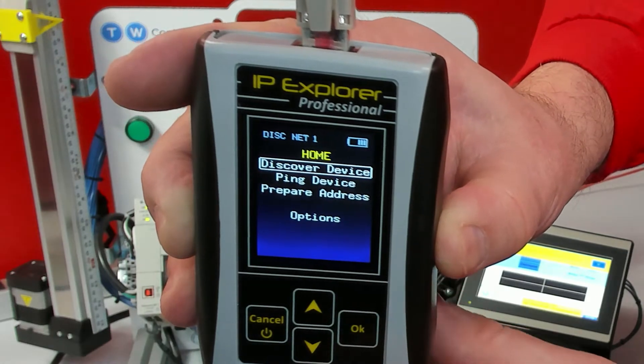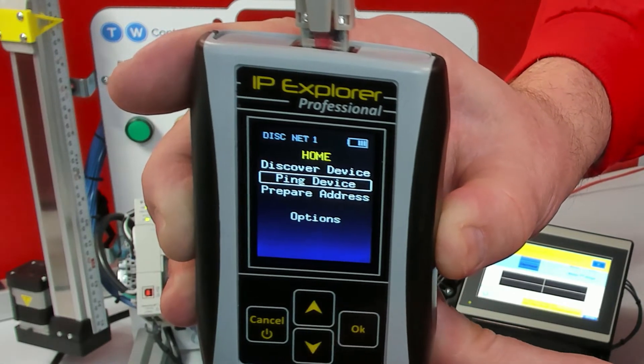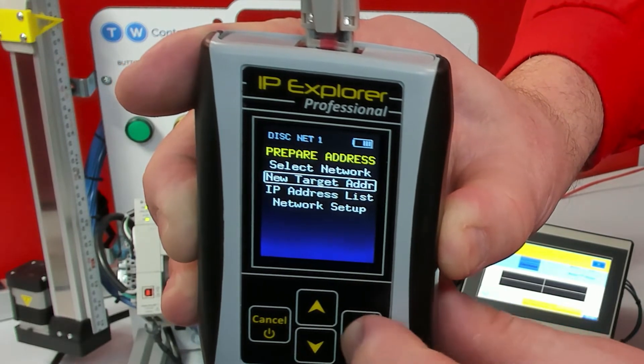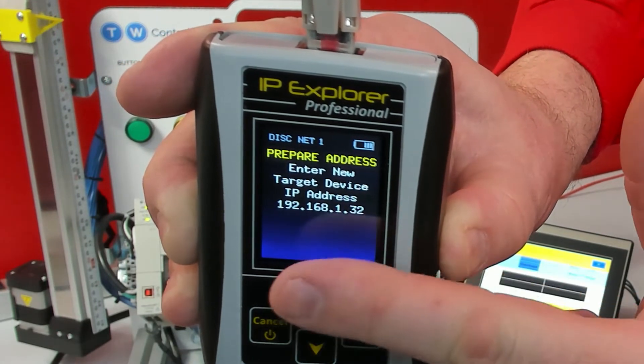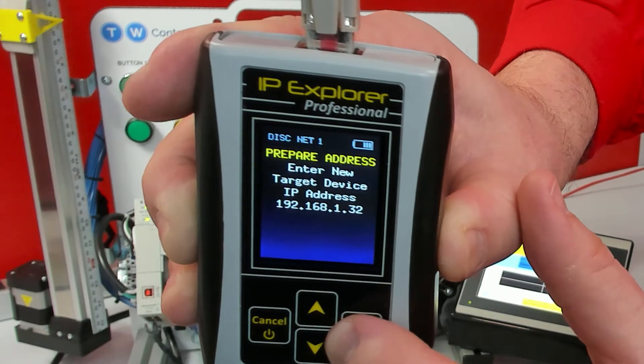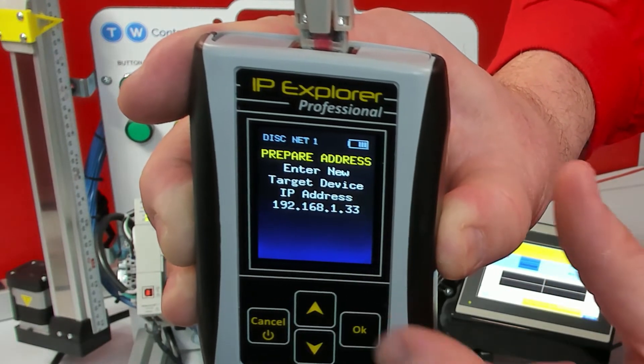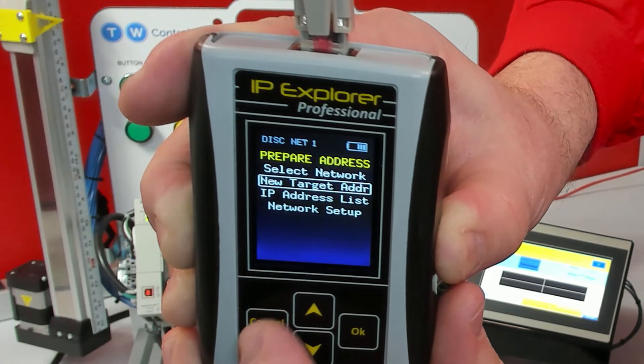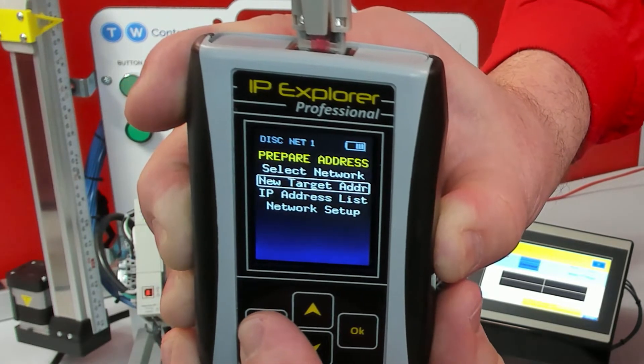Before we power up the SMC, we're going to go down to Prepare Address and set a new target address. For this one, we are going to use 192.168.1.32. The only reason we have to do that is because the SMC gives us just a little bit of time for the DHCP assignment initially.